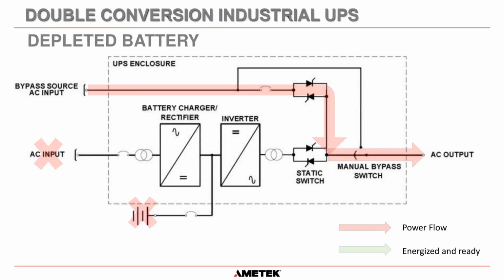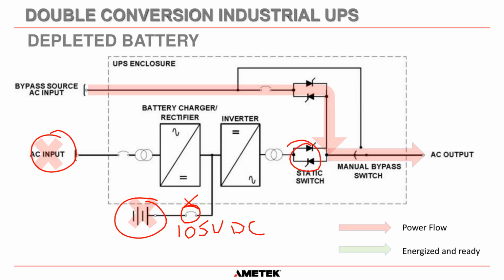And then once we get down to the battery end of discharge level, which on our systems is usually 105 volts DC for a 60 cell system, then this battery breaker here, it's actually inside the UPS, trips. And before it does that, it switches the static switch from inverter to load to bypass to load. So the bypass source will go through the static switch out to the AC output, and then this static switch will turn off, and then this breaker here will trip.